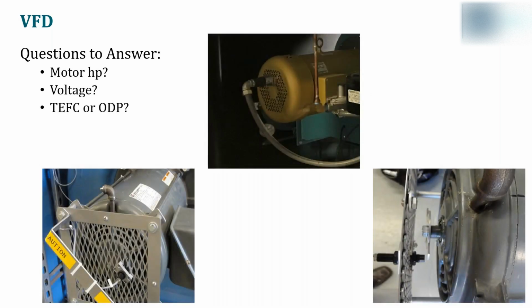In terms of VFD, the questions you need to answer are: what is the motor horsepower? What is the voltage? And is it a TEFC or ODP motor? And finally, is it normal or heavy duty? One thing to keep in mind here: if it is a normal duty motor, it may or may not be able to accept the VFD. That's something you will have to check with the manufacturer.